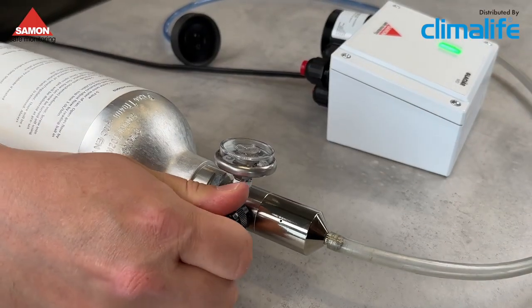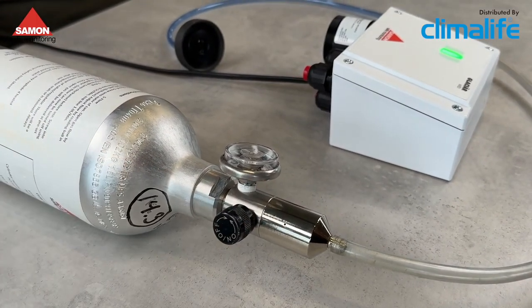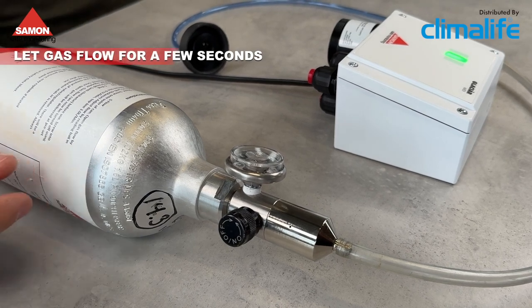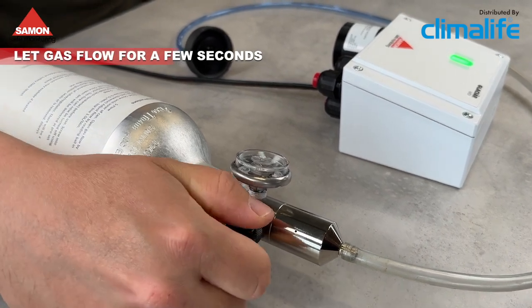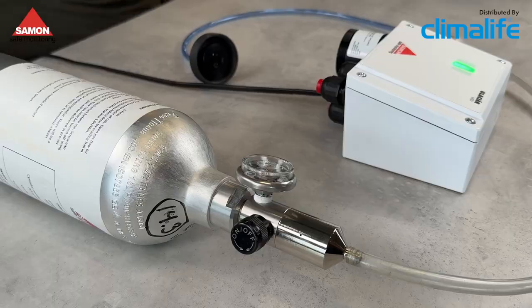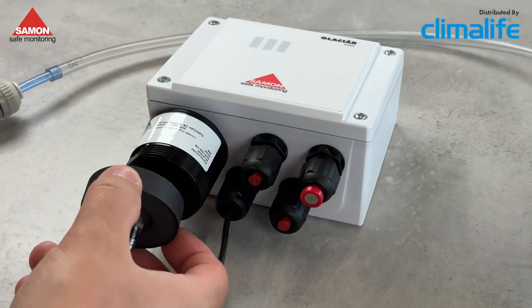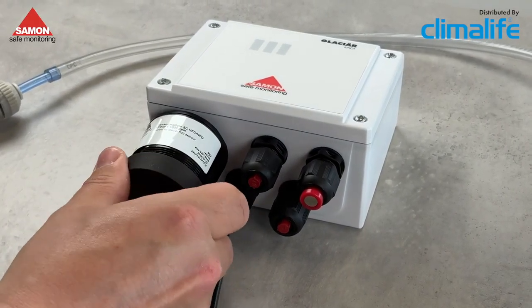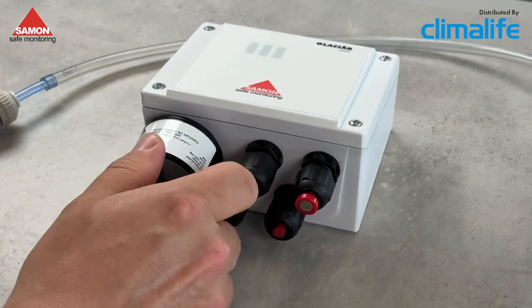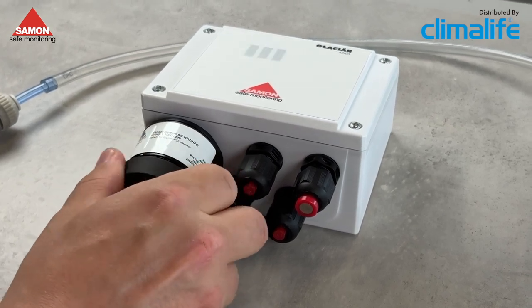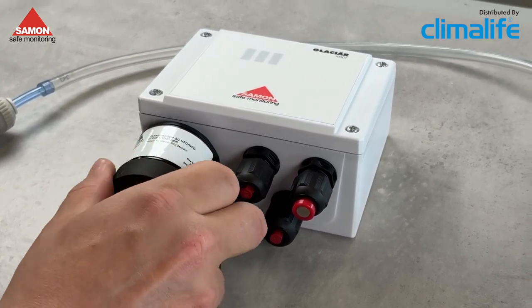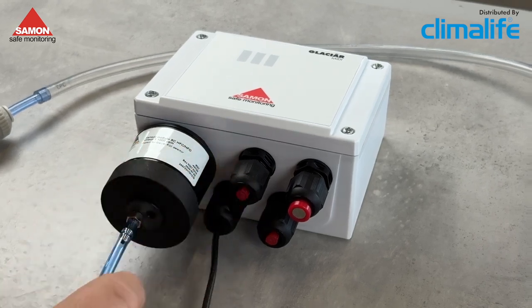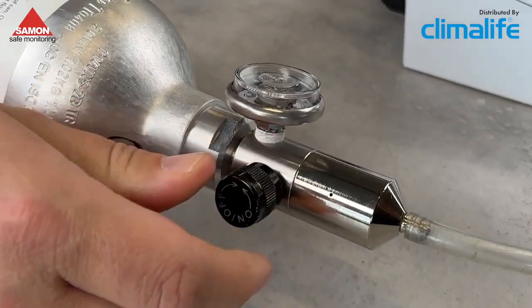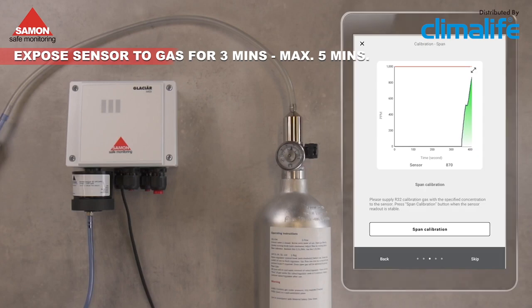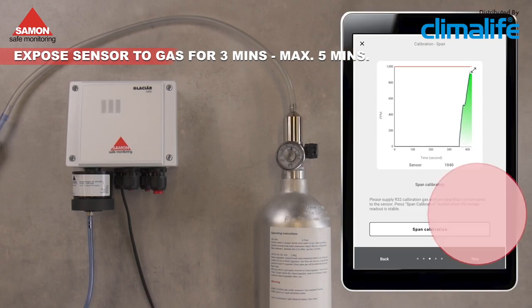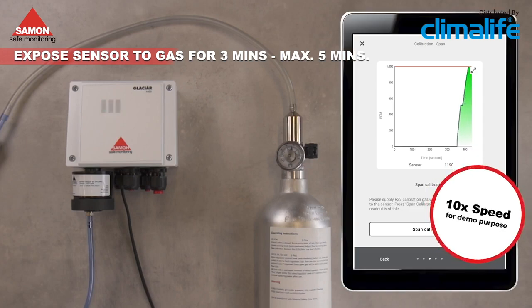Turn on the regulator, which has a fixed flow of 0.5 liter per minute, and let the gas flow for a few seconds without the calibration adapter connected to the sensor. Now mount the calibration kit onto the sensor module. Screw it on firmly. Let the gas flow over the sensor. Expose the sensor to the gas for about 3 minutes until it stabilizes at the preferred level.